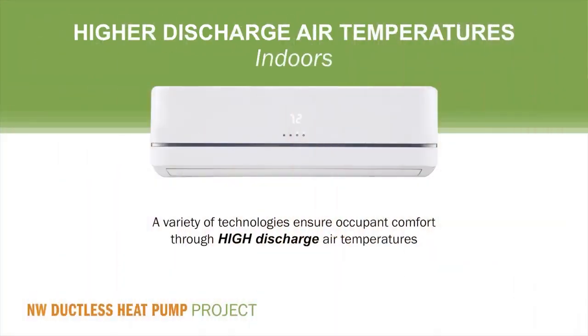In addition to being programmed for cold climates, this new generation of heat pumps are designed to operate primarily as heating appliances. They are engineered from the ground up to produce heating comfort, and chief among these heating features is high discharge air temperature. Hot discharge air is combined with other air circulation features that are intended to make occupants more comfortable than any other technology available.